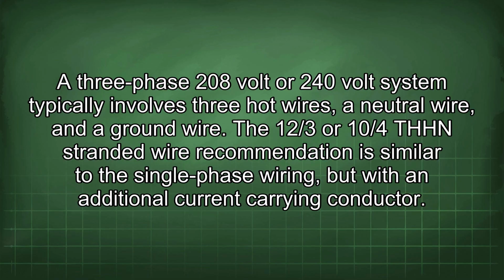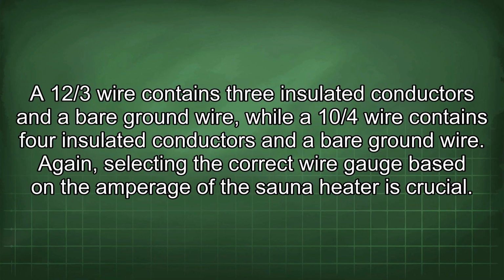The 12/3 or 10/4 THHN stranded wire recommendation is similar to the single-phase wiring, but with an additional current-carrying conductor. The 12/3 wire contains 3 insulated conductors and a bare ground wire, while a 10/4 wire contains 4 insulated conductors and a bare ground wire. Again, selecting the correct wire gauge based on the amperage of the sauna heater is crucial.